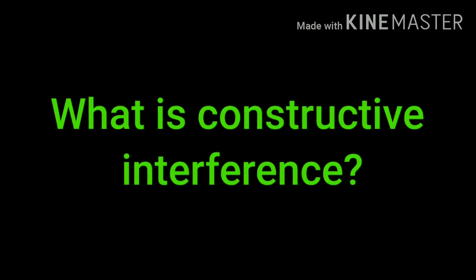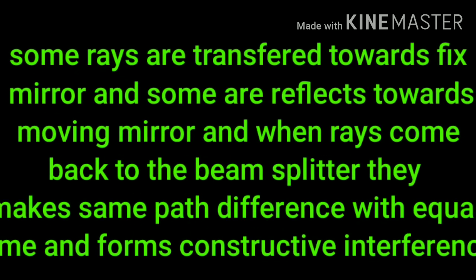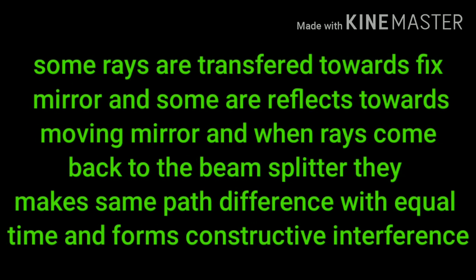Let's understand constructive interference first. FTIR has two mirrors — one fixed mirror and one moving mirror, both at equal distance. When infrared light hits the beam splitter, it splits the beam rays. Some rays travel towards the fixed mirror and some are reflected towards the moving mirror. When the rays come back to the beam splitter, they travel the same path distance in equal time and form constructive interference.